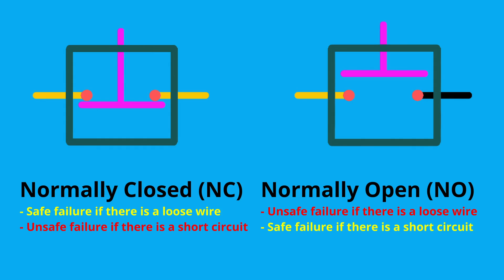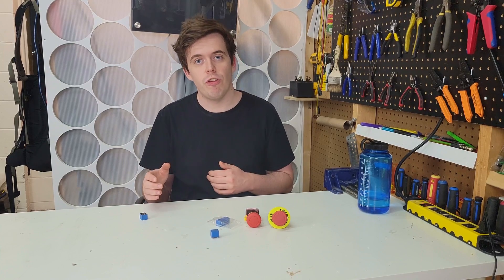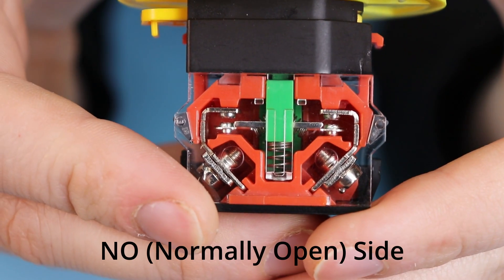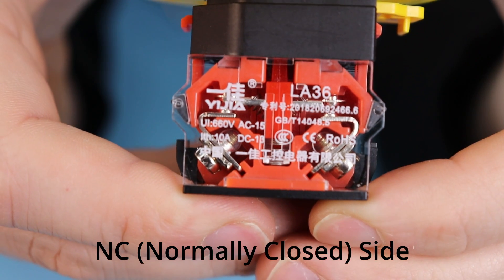So in summary, the normally closed and normally open switches have opposite failure modes. A normally closed switch will fail in a safe manner if there's a loose connection, but will fail in an unsafe manner if there's a short connection, and vice versa for a normally open switch. That's why, for the most robust implementation of an emergency stop button, you should use one that has both normally closed and normally open modes, such as this emergency stop button.